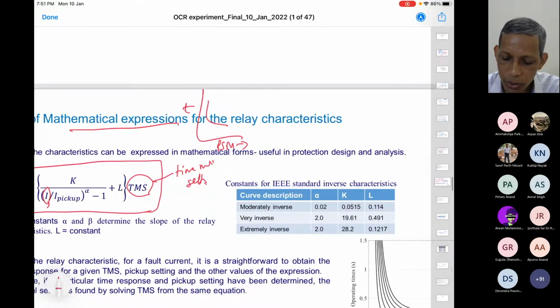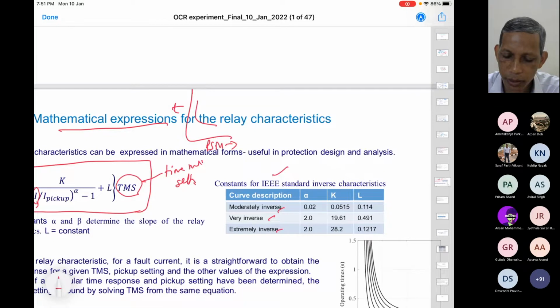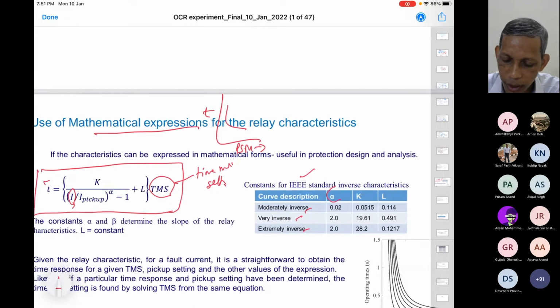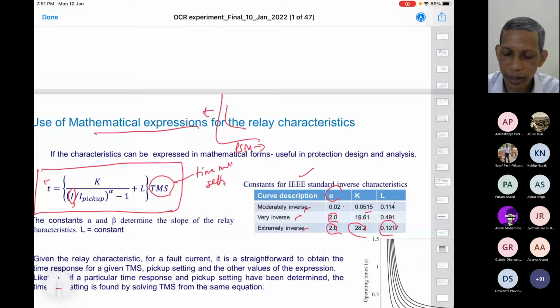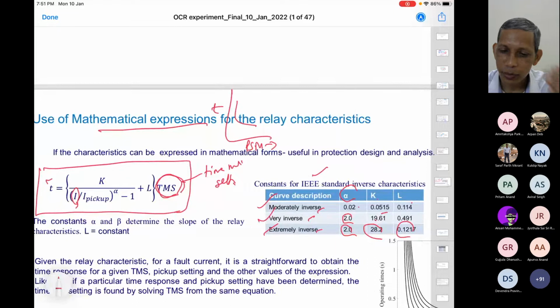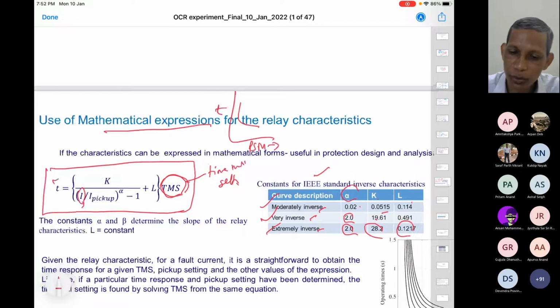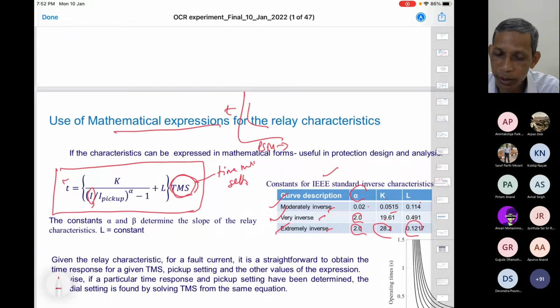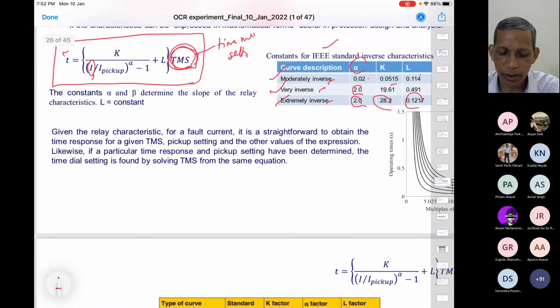For the corresponding IEEE curves, moderately inverse, very inverse, and extremely inverse, the expression has alpha 0.02, K 0.05, and L 0.114 for moderately inverse. We put in these corresponding values, which are already standardized and given by the manufacturer, including in the IEEE material also. Then whatever curve we get is called moderately inverse, very inverse, or extremely inverse. And you multiply the TMS like 0.1, 0.2 to 1.5, depending upon the availability in the particular relay. You can again control the corresponding time. You can make it faster if you multiply with 0.1, and delayed if you multiply with 3. These are the options you can have. And why do you require that? We'll see later. Okay.